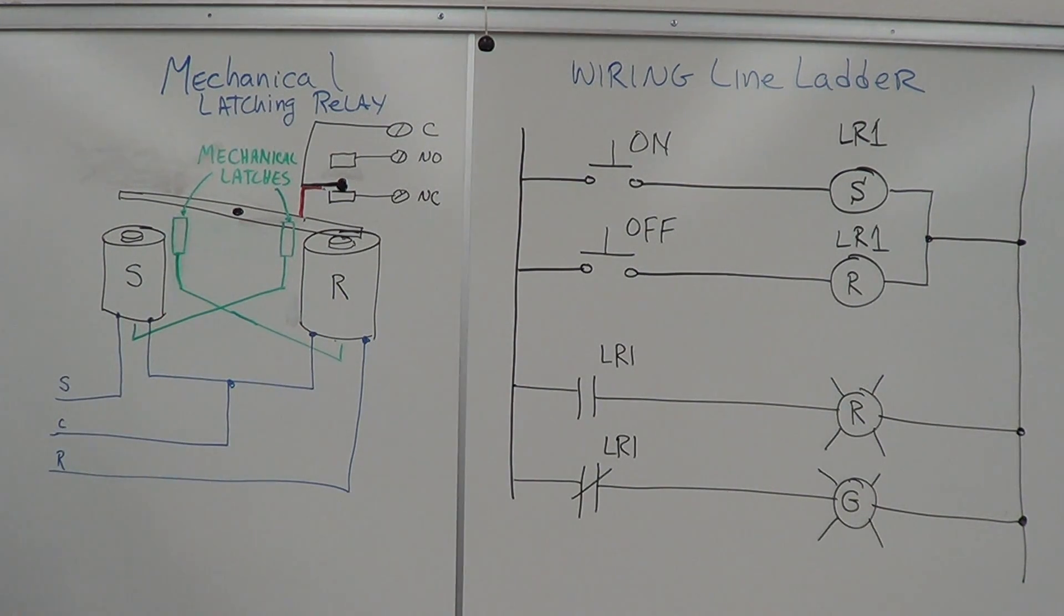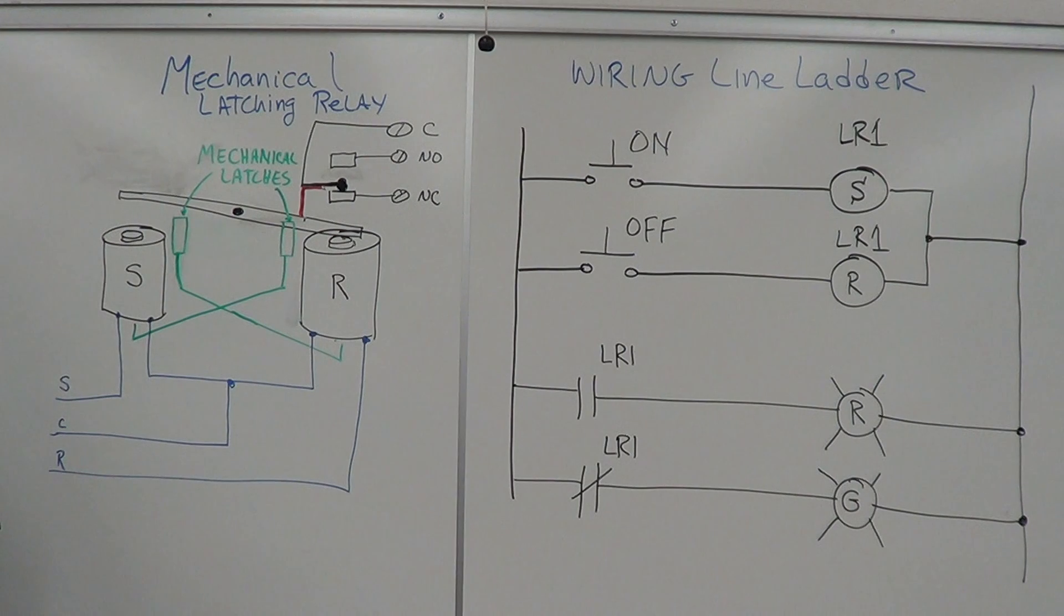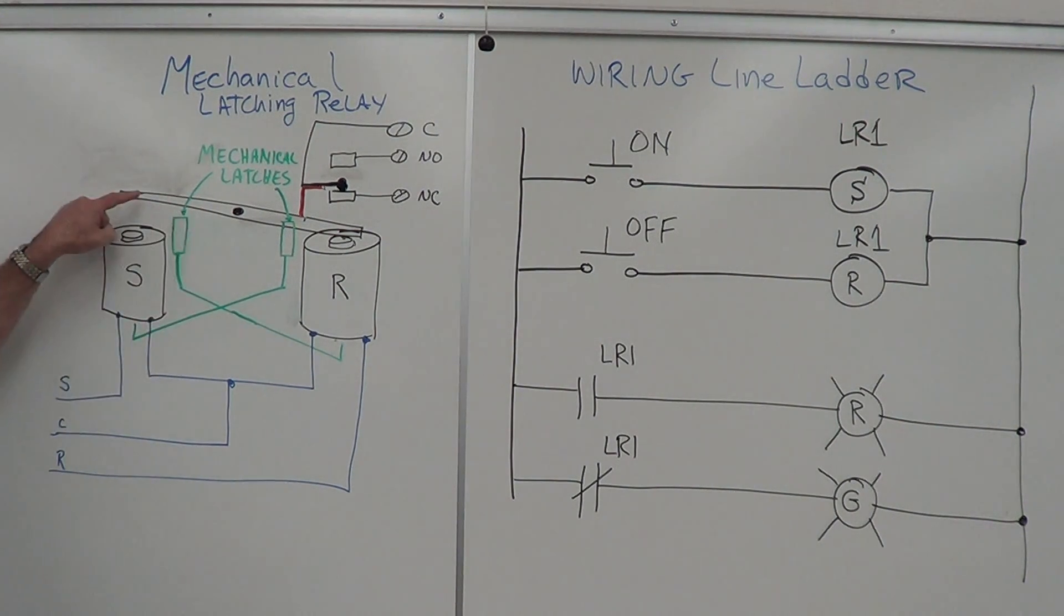You have a mechanical setup in here that holds your lever either in the off position or the on position. Right now it's set up in the off position. If I energize this coil here, the coil will release the mechanical latch and pull the lever down and hold it in place.